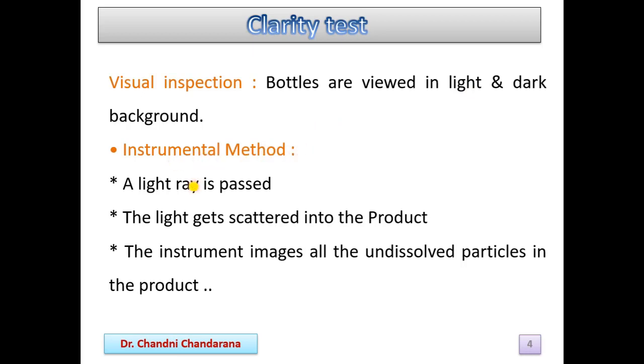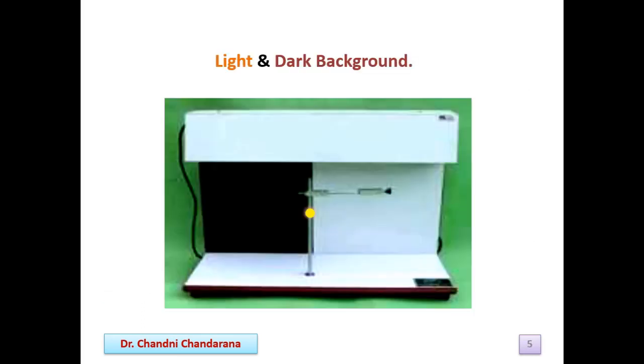For the instrumental method, we pass light through the product and the light gets scattered by particles inside. The instrument images all the undissolved particles in the product. Here we can see there is a light background as well as a dark background, and we put the sample there to measure it.